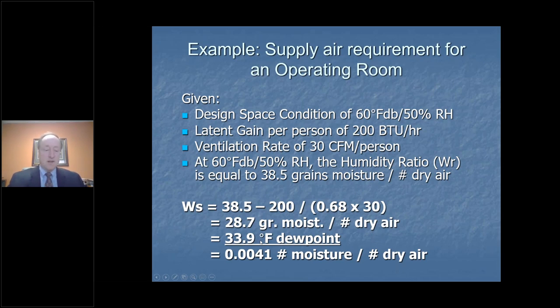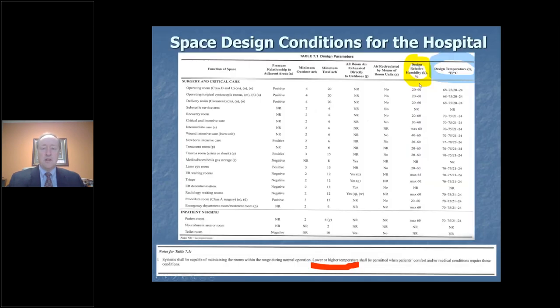So that's a significant difference when you drop down from a patient room to an operating room. This is a table that you'll see out of the healthcare design book from ASHRAE, and you look over here at the design relative humidity numbers, and here you have the design temperatures. You look for operating rooms over here, and it shows 20 to 60%.